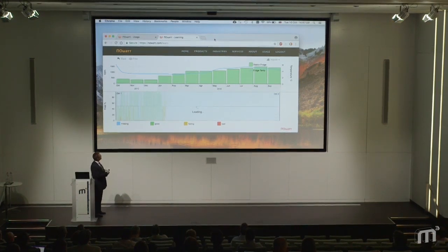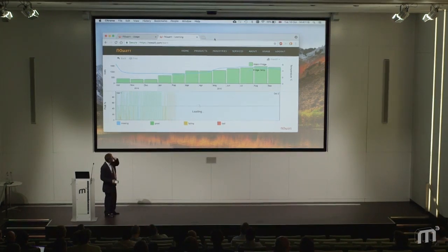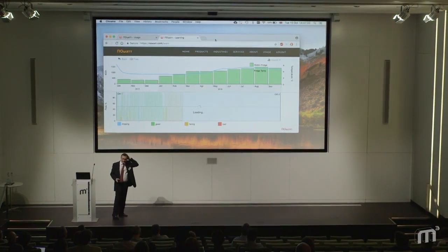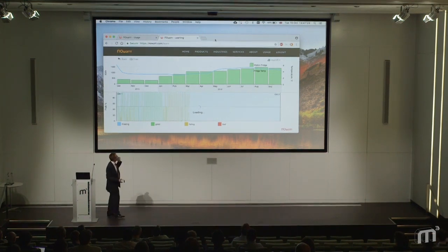Here the AI saw a change in the pattern, and it's predicting this. So if we ran the report at the end of January, we'd see that there was a fairly 90% chance that we were looking at a failure in progress. You know, this thing could fail in the next 8 months.